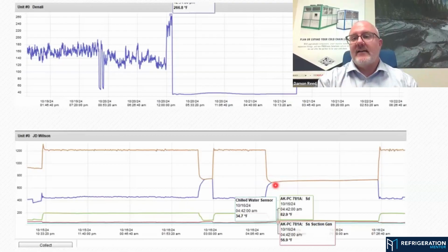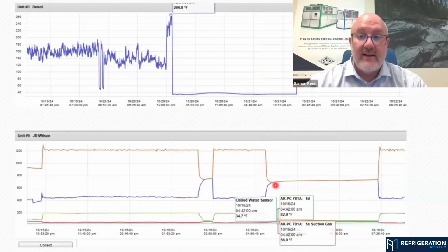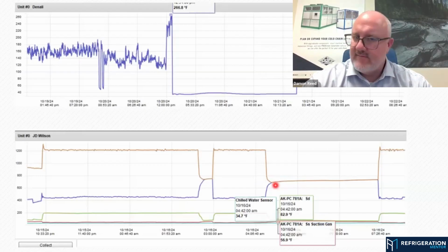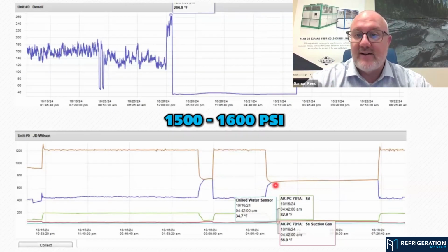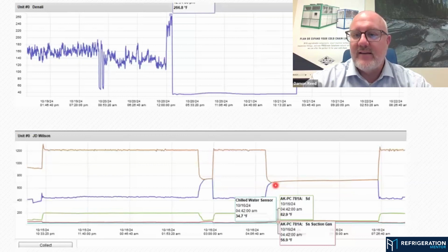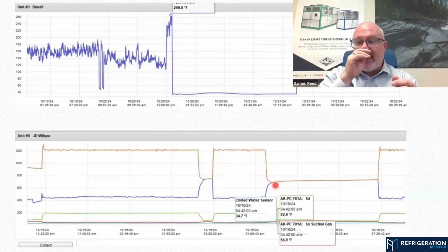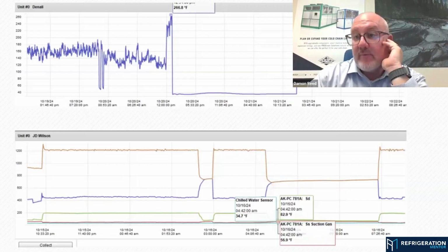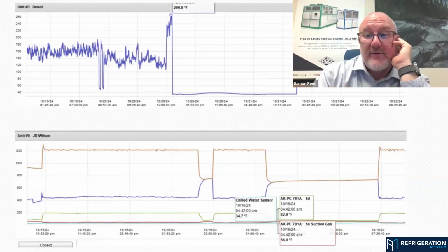Okay, well, I've got to get out on site. And when I say I, I don't mean I personally, I mean the mechanic, the technician that services the equipment, goes out on site to see if these pressures are right. Is this making sense? And in this case, we were actually getting up to 1500, 1600 psi, but there was a faulty discharge pressure sensor. It just wasn't reading accurately. So that you can verify that. That's when you make that call to get on site. But the remote diagnostics kind of already pointed the direction.